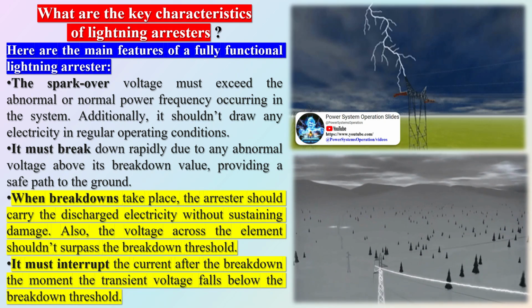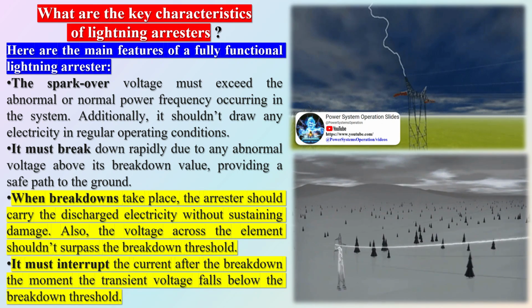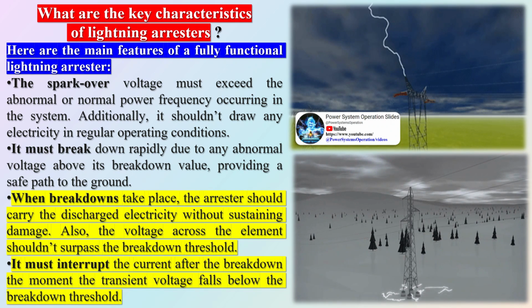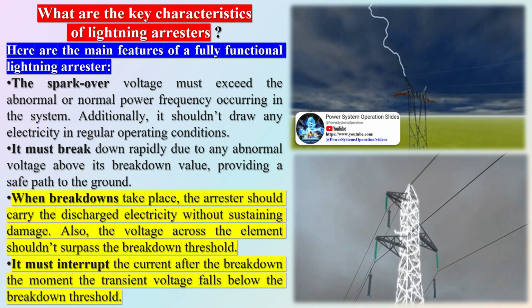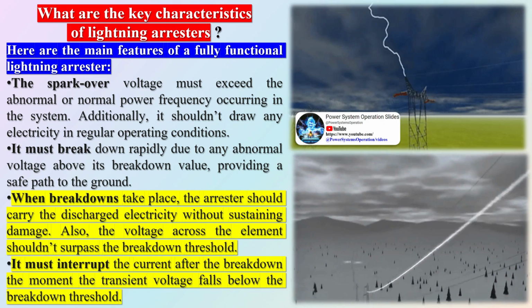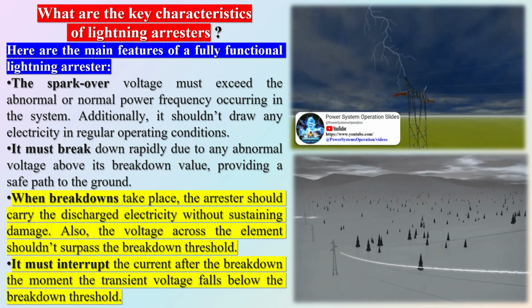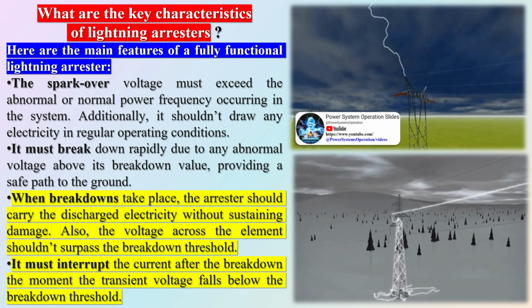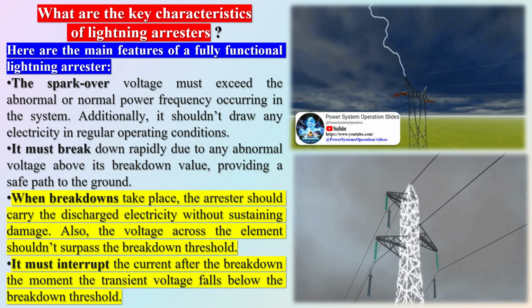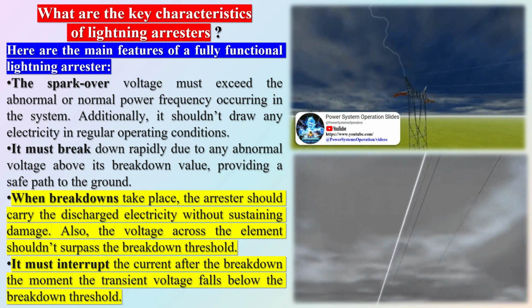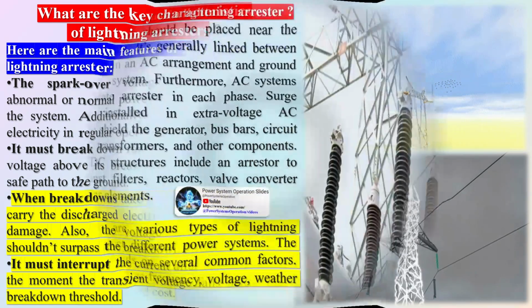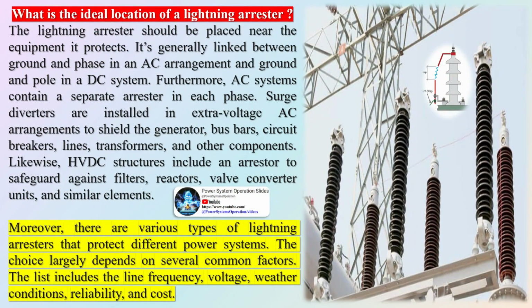However, when a lightning-induced surge raises the line voltage momentarily above the arrestor's rating, the varistors start conducting and provide a low resistance path to earth. This allows the surge current to be diverted harmlessly to the ground, thus preventing excessive voltage spikes from damaging equipment on the protected side. Once the surge passes, the varistors again become non-conducting.